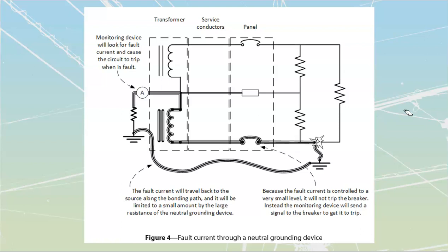So although this is not common on single phase, there are very few places where it could be, but it is a requirement of the ITA that for harmonized electricians you know about what these things are, just in case you run into them, so that you don't do anything dumb with these. They are going to have warning signs all over the place, but what they are is a giant resistor that's going to be placed into the grounding conductor itself. And that is going to drop my total amount of current that I'm going to travel through there, right? I'll actually write it out as the current formula.